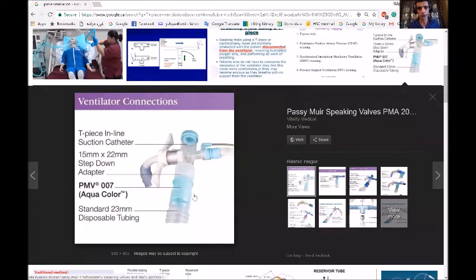Do you see this now? Yes, exactly the same. Here is this piece connected to the mask and this one connected to a pressure generator oxygen at the same time. This one has a valve you can see, so you can set this valve to achieve a PEEP.